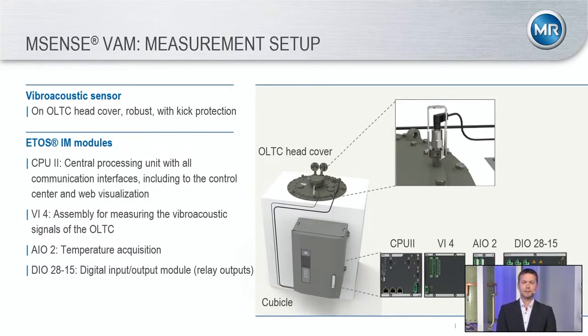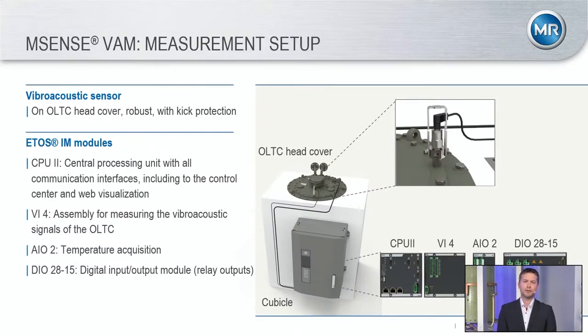There also needs to be a temperature measurement card installed, because the temperature of the transformer or tap-changer oil has an influence on the behavior of the acoustical curve. Furthermore, we need a digital I/O card to be able to measure the tap position and output alarm statuses via hardware signals.